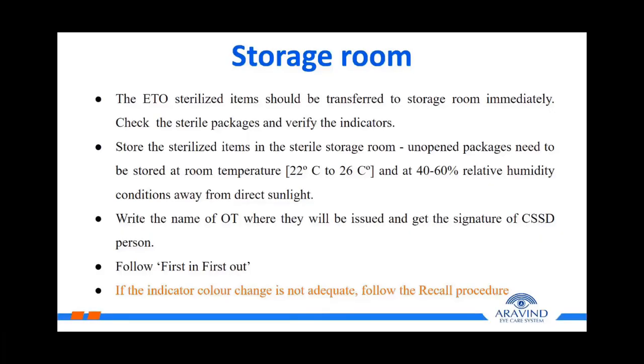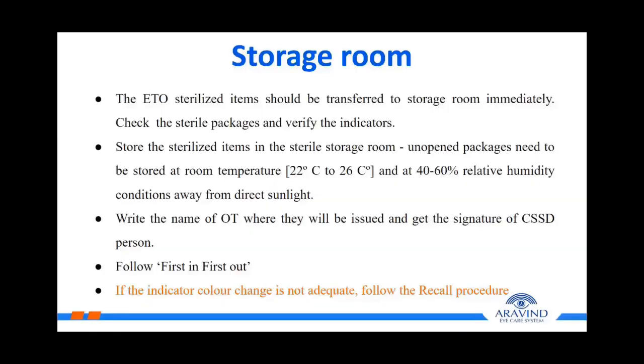The ETO sterilized items should be transferred to the storage room immediately. Check the sterile packages and verify the indicators. Follow first in, first out, that is, the accessories put first are to be used first. Store the sterilized items in the sterile storage room. Unopened packages need to be stored at room temperature, that is 22 to 26 degrees Celsius, and at 40 to 60% relative humidity, away from direct sunlight. Write the name of the OT where they will be issued and get the signature of the CSSD person. If the indicator color change is not adequate, follow the recall procedure.